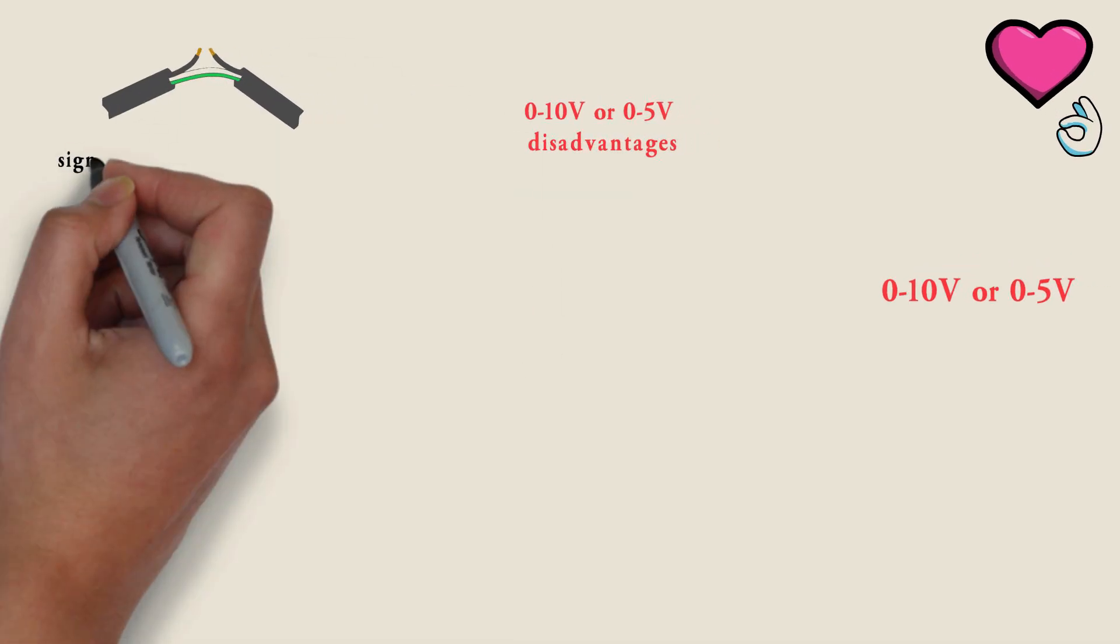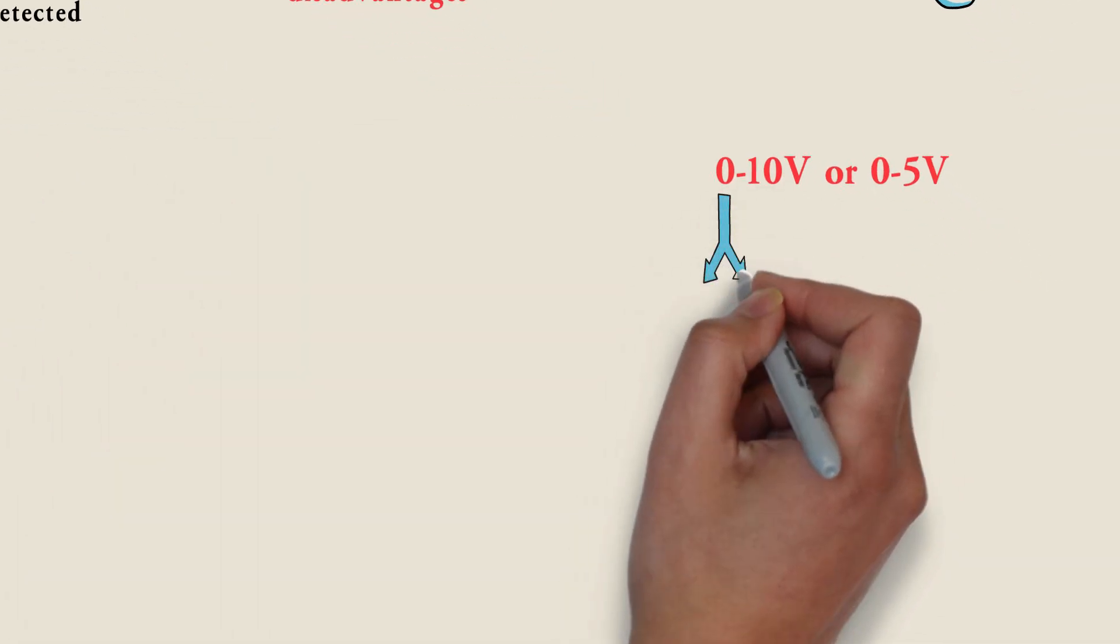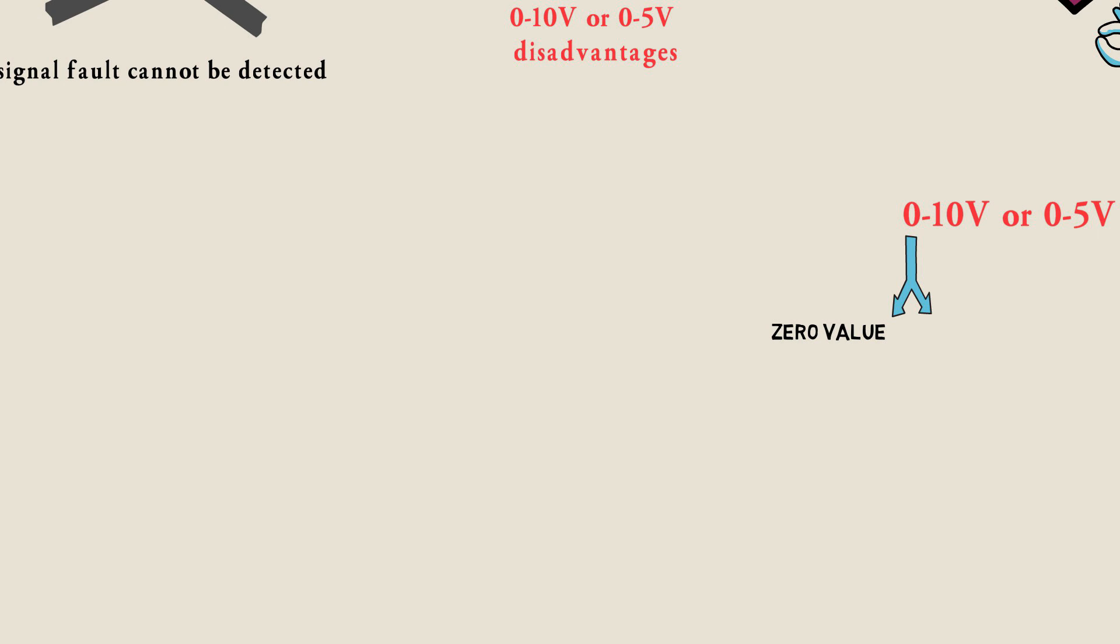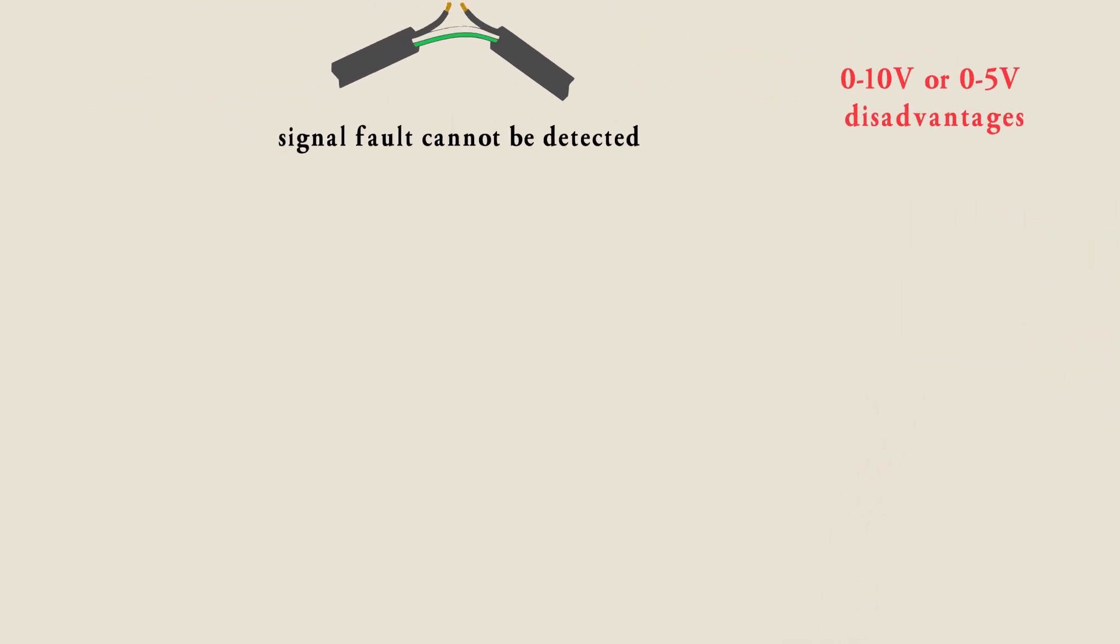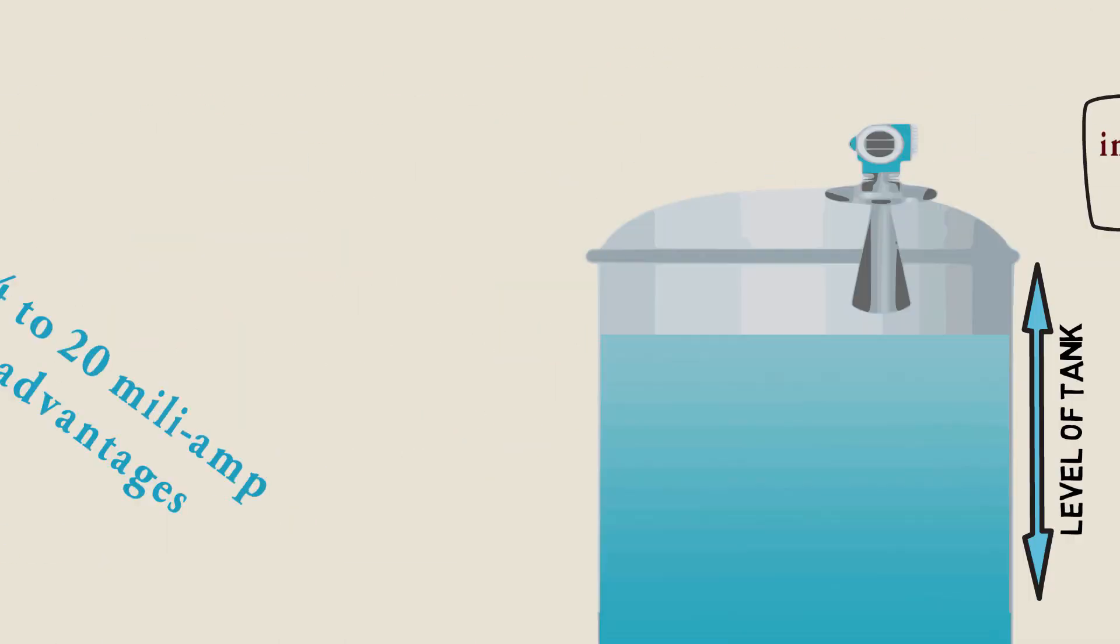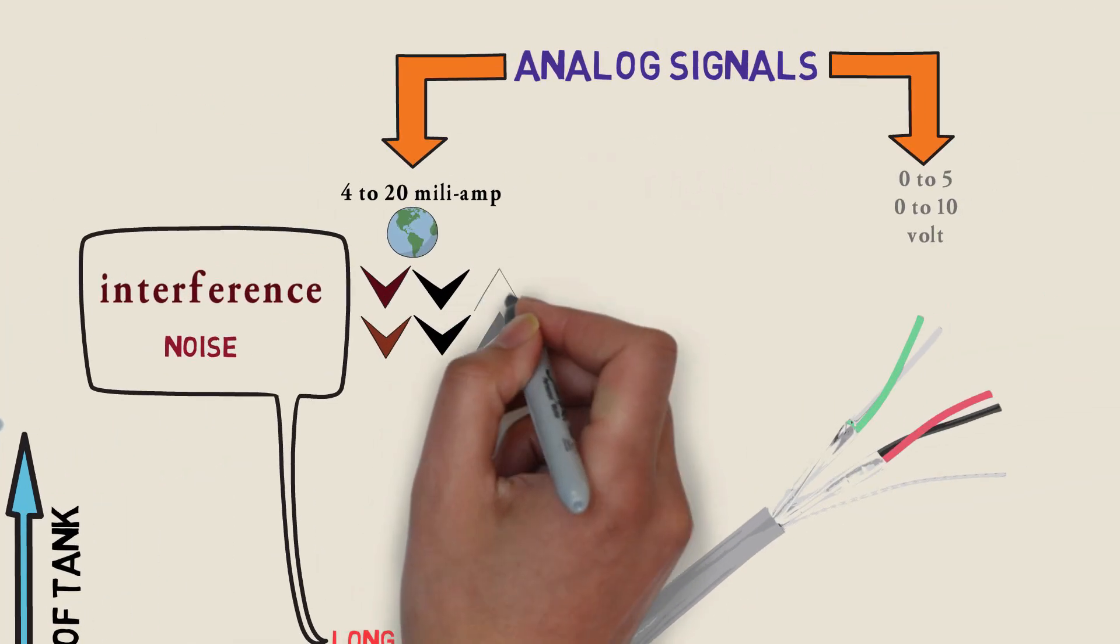A 0 to 10 volt or 0 to 5 volt analog signal has some disadvantages, including: a sensor signal fault cannot be detected. A value of 0 volt can indicate either 0 value or no signal. Over longer cable distances, voltage drop can cause an inaccurate signal. And it's prone to electrical noise and interference.